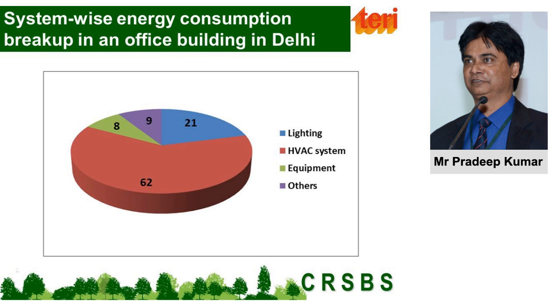And as I started discussing with you the different load points and how they are defined, the different energy systems which are installed in a building and how much they consume. Let's say, for example, an office building, and this is the averaged one, not a typical office building, which is centrally air conditioned. Lighting consumes somewhere around 21%, air conditioning 62%, equipment 8%, and others 9%. So roughly you can say that the lighting and HVAC systems or air conditioning system consume 80% of the total energy consumed in an office building which is centrally air conditioned.